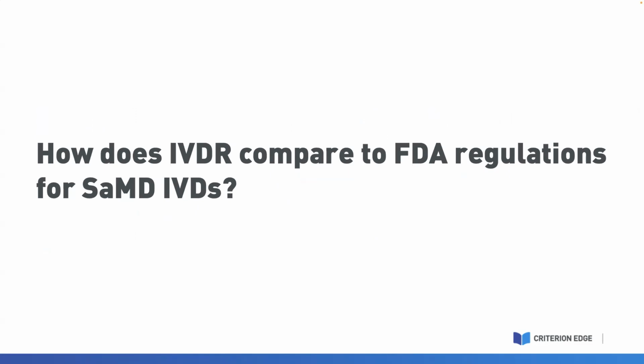According to the BSI group, they classify and describe the main differences between the FDA regulations and the EU regulations for software. The biggest thing is going to come down to how you classify and group it, because the EU considers software as an IVD device, whereas the FDA tends to use more of a risk framework to clarify what software is not in the scope of its regulation. And the EU uses the function of the software.